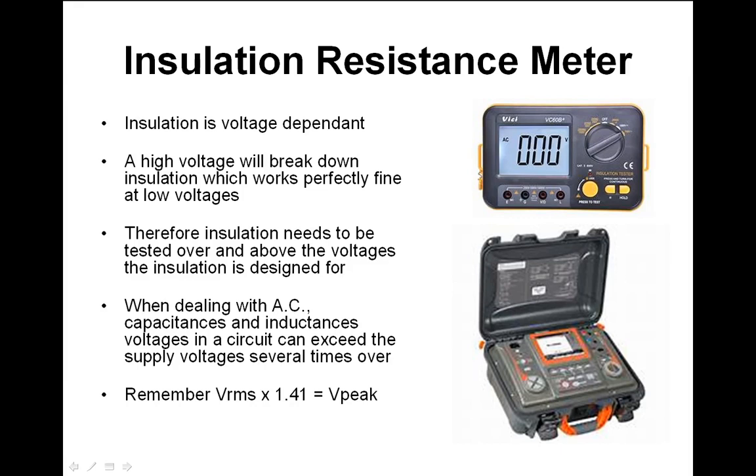The main thing about insulation testers is it's the whole thing about voltage. High voltage, eventually insulators will break down. And you just need to make sure that they don't break down at the voltage you apply. When you look at three-phase motors, for example, all you have on the coils is a little bit of lacquer. They put some lacquer, some enamel on the wire they use for the coils, and then they wind them together. And that's all done in an industrial process. And if there's a problem with the lacquer, the enamel type of stuff that's on the wires, the insulators can break down quite easily, so that's one problem.